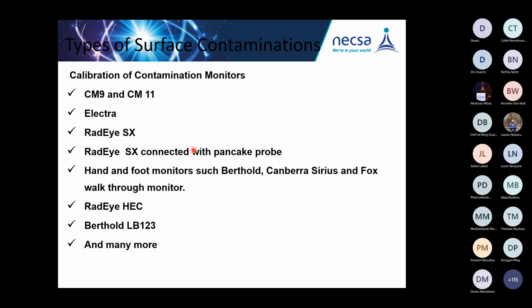Also, when an instrument undergoes a repair, the question is: do I have to resend my instrument for verification or for recalibration? And when do I have to take my instrument for recalibration? Only when you replace a major component part. If you replace the whole circuit board, unlike with these ones that we always see these days, then you have no option except to recalibrate your instrument. If you replace your Geiger-Müller tube, your instrument must be recalibrated again. If you replace the PM tube, your instrument must be recalibrated again. So you will understand those dynamics.